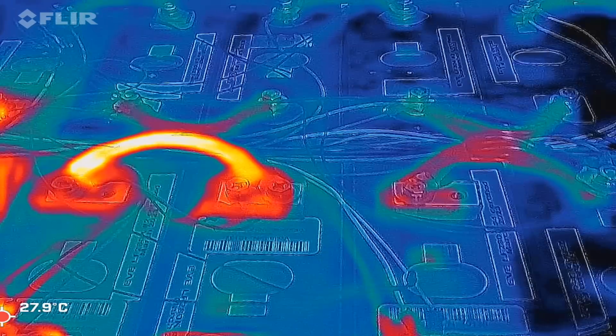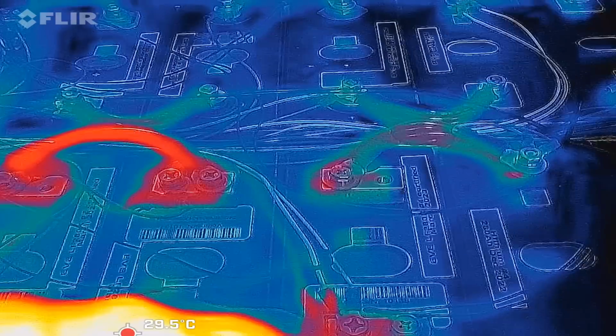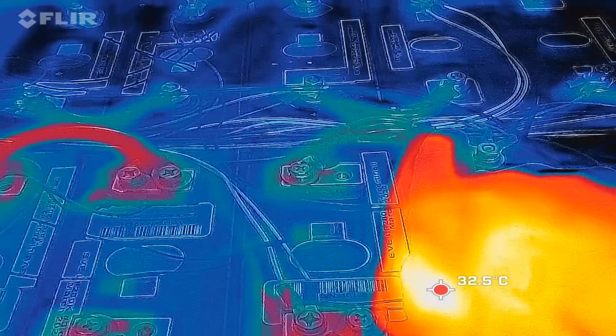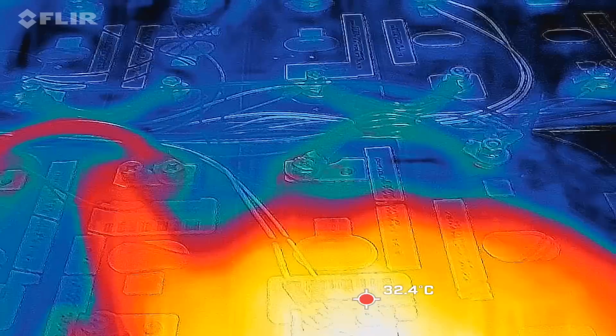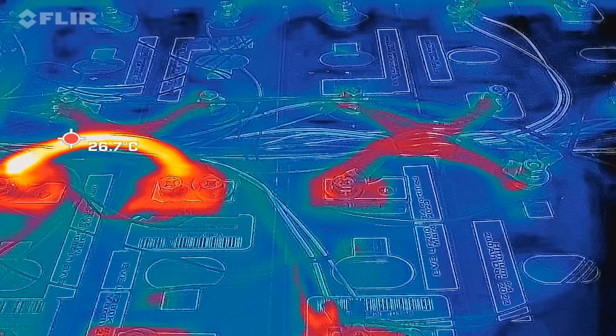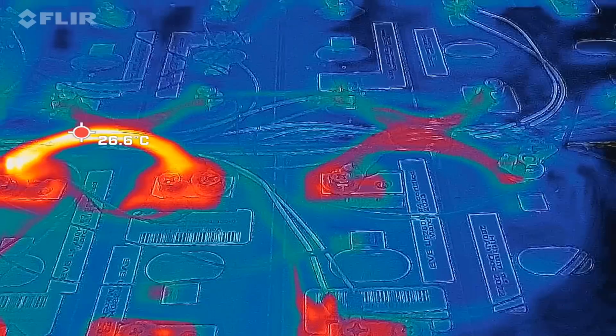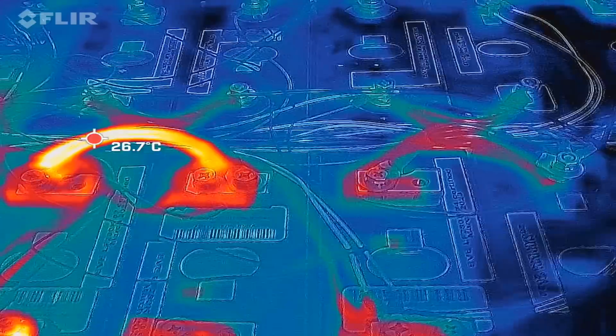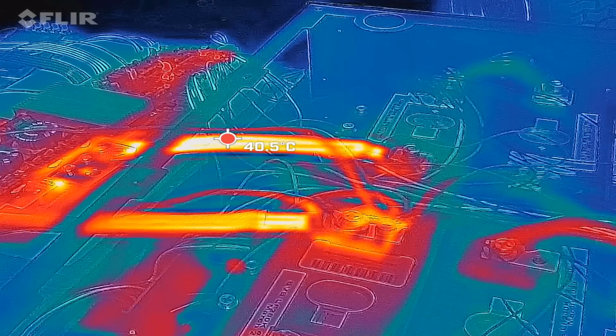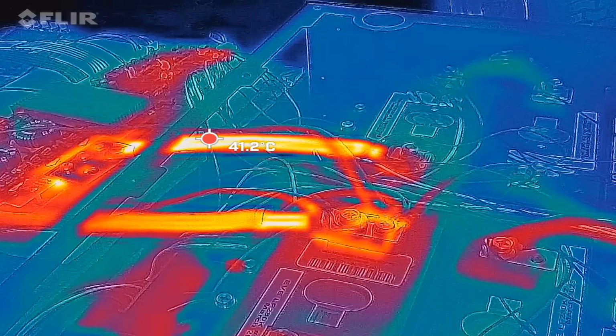Whenever people see these infrared pictures, they say oh, this is far too hot, far too hot. This is actually 2 degrees difference between this bus bar and this bus bar, and this one looks cold while the other one looks really hot. But this is just what the picture says - if you compare the actual temperatures, it is only 1 or 2 degrees difference. I still consider this as okay-ish at 40 degrees at 100 amps.